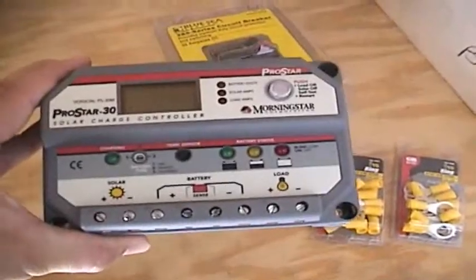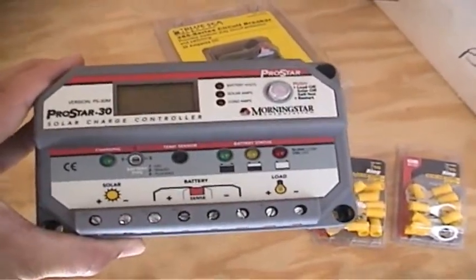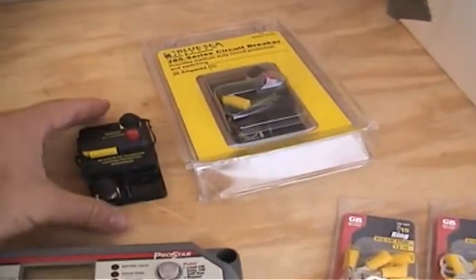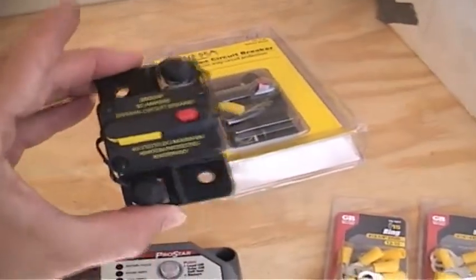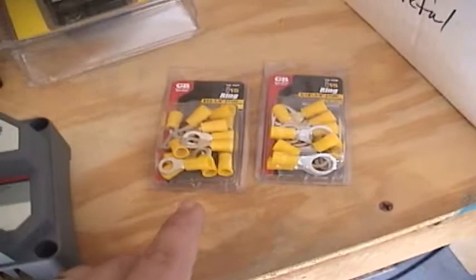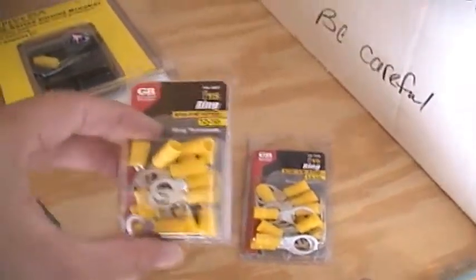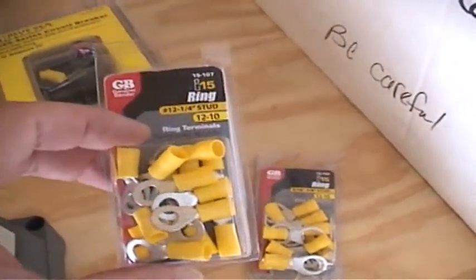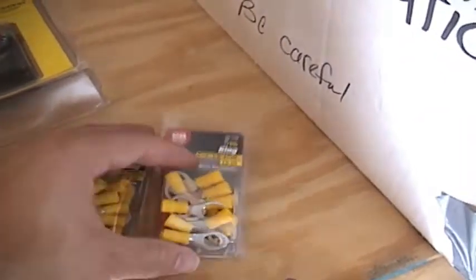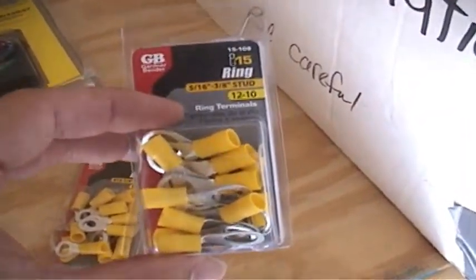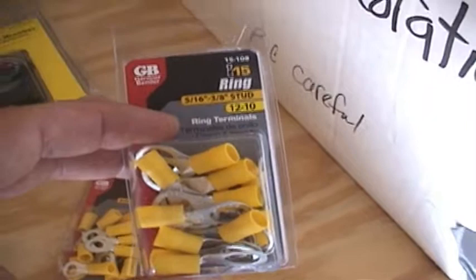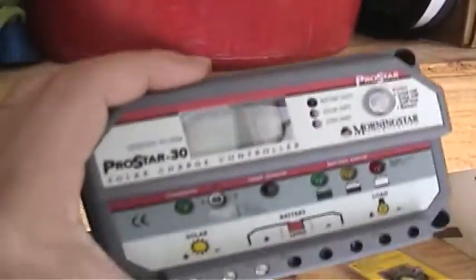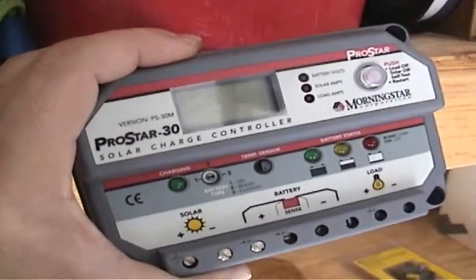To begin our next step, we're going to need our ProStar 30 solar charge controller, our two 30 amp circuit breakers, and 2 packs of ring terminals. The first one fits 10 gauge wire and a 1/4 inch stud. The second one fits 10 gauge wire but 5/16 to 3/8 of an inch stud. Let's begin with the solar charge controller.